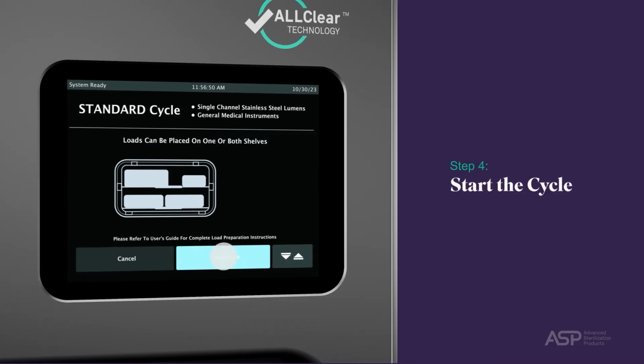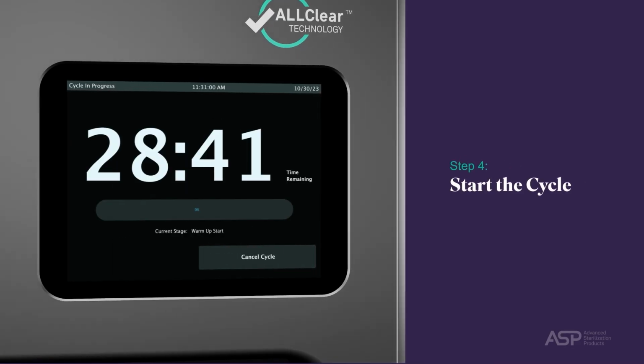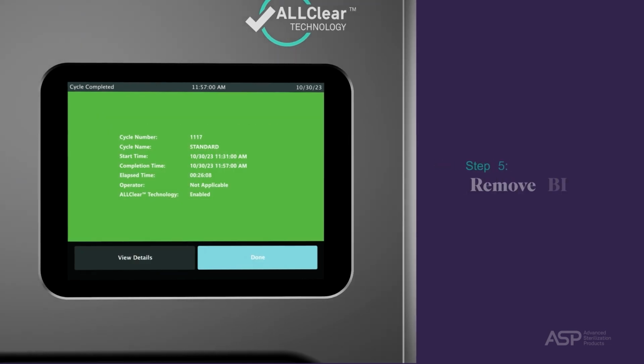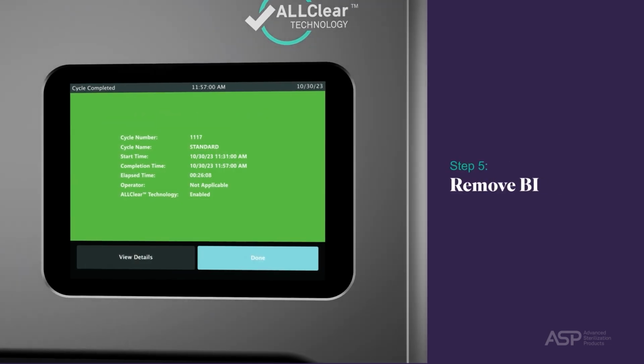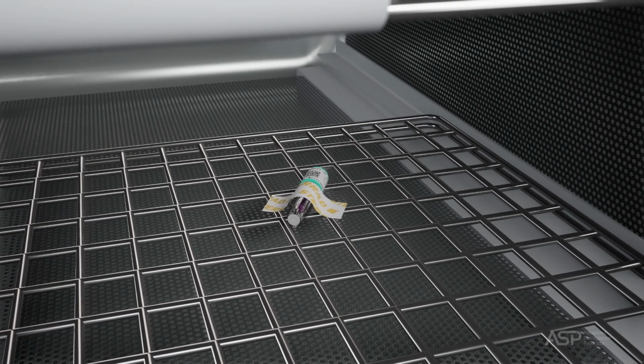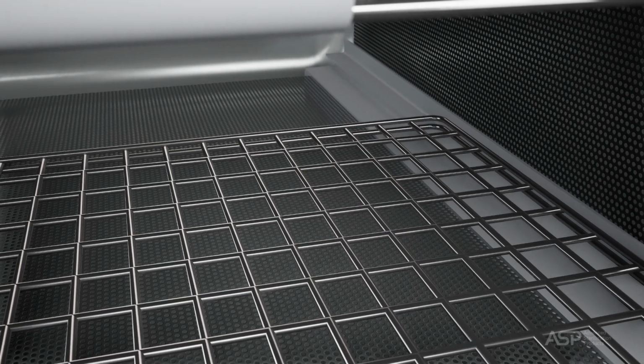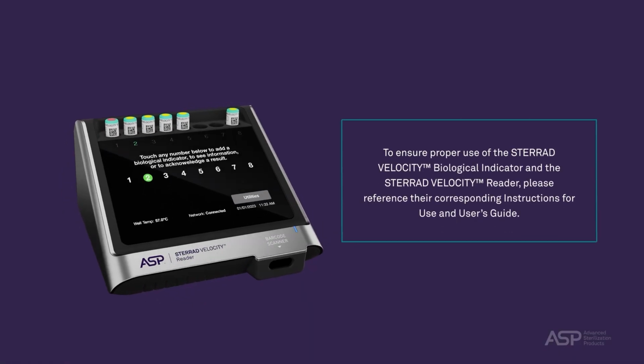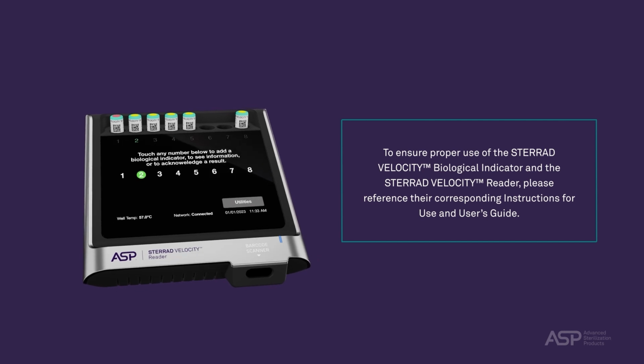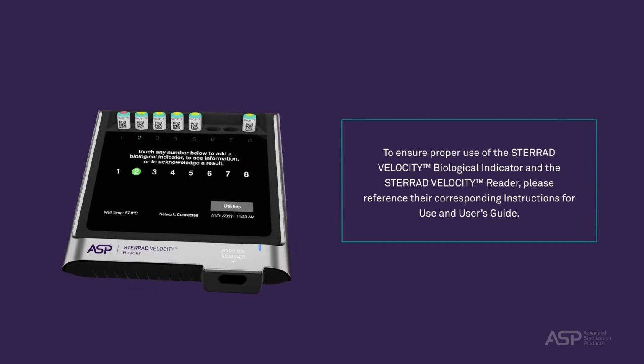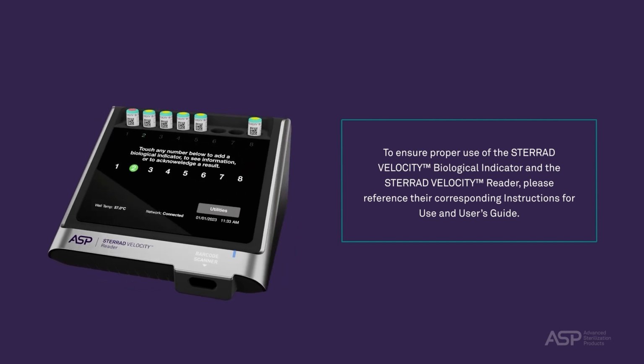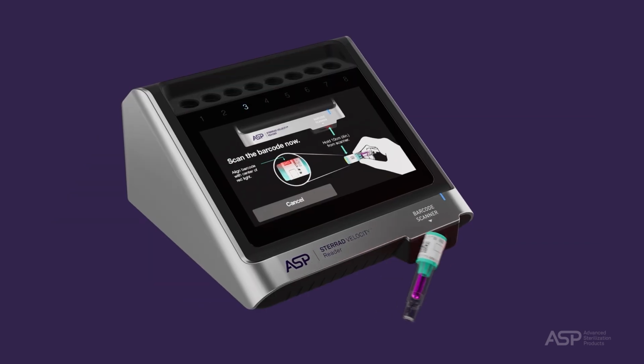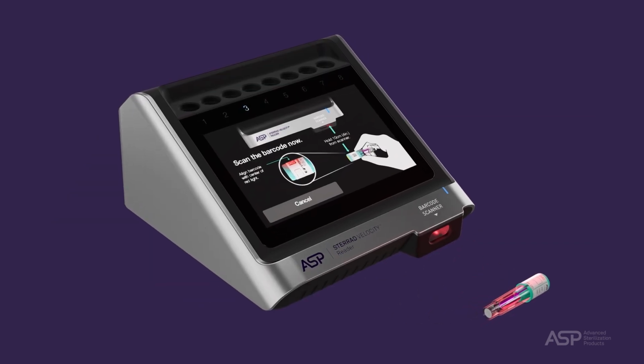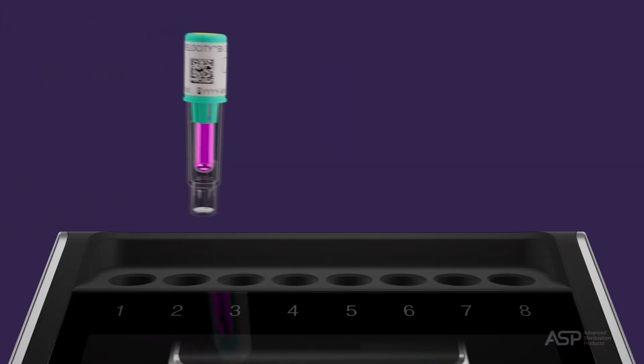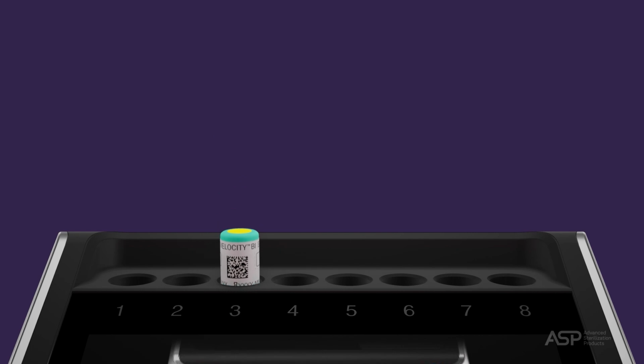Step 4. Start the cycle and wait for the process to complete. Step 5. Once the cycle completes, put on protective gloves and remove the BI/PCD from the chamber. To ensure proper use of the STERRAD Velocity Biological Indicator and the STERRAD Velocity Reader, please reference their corresponding instructions for use and user's guide. The BI must be placed in the STERRAD Velocity Reader within the time frame specified in the instructions for use.